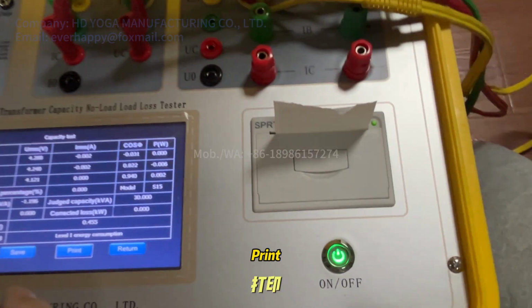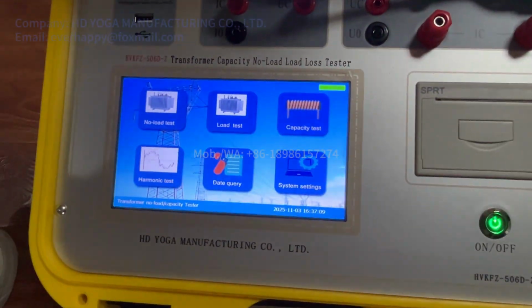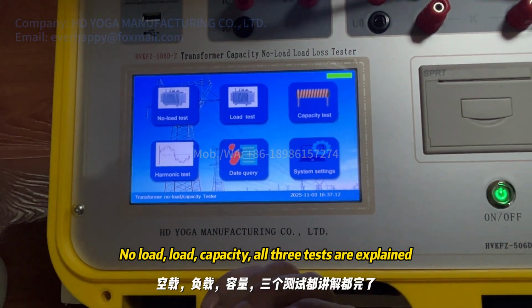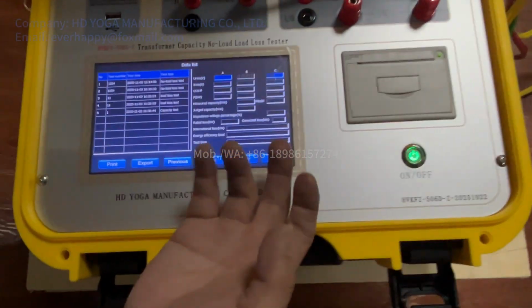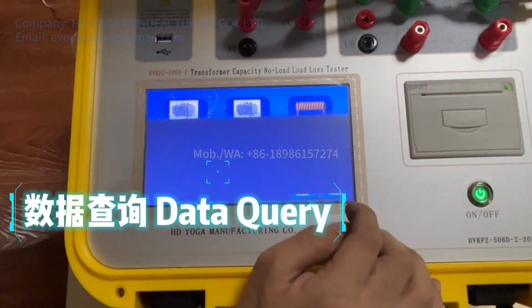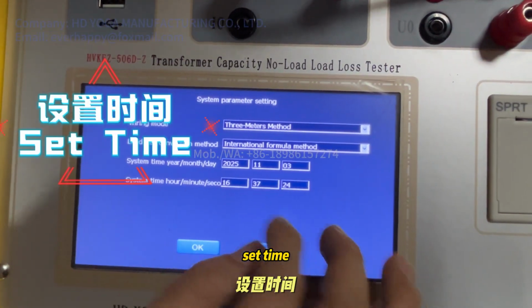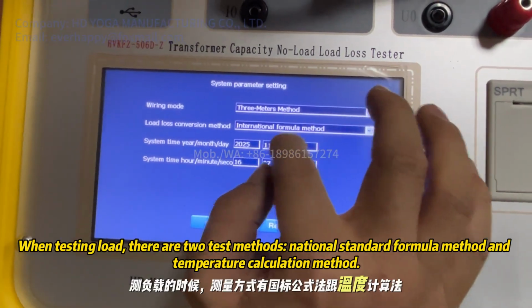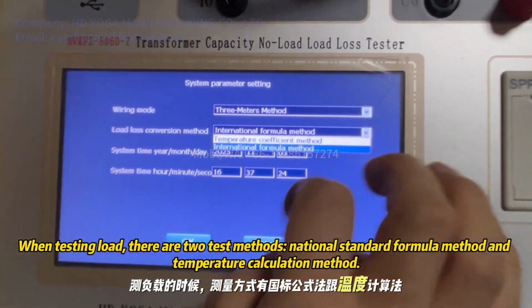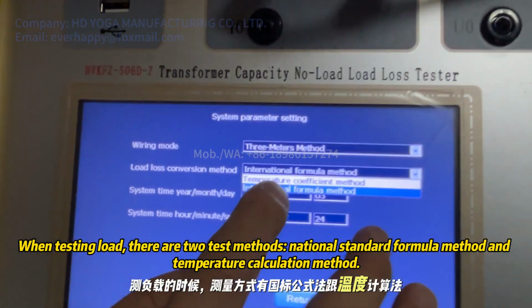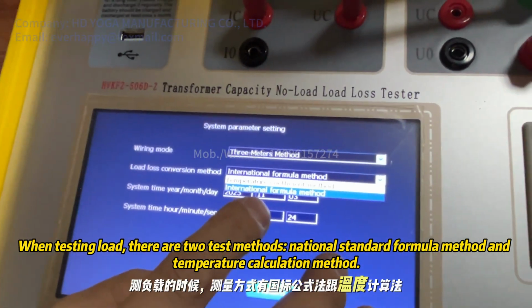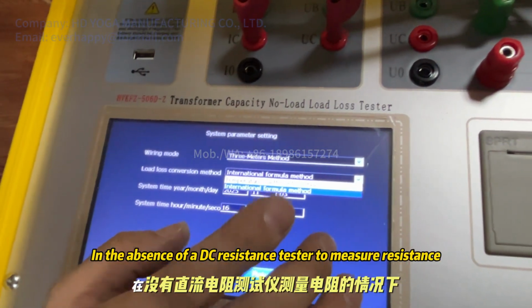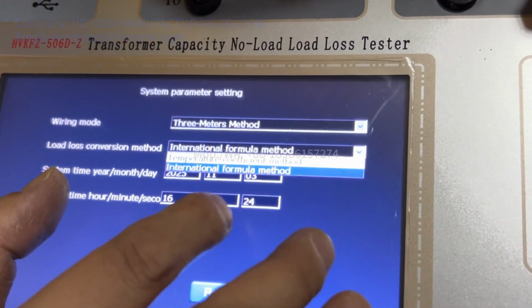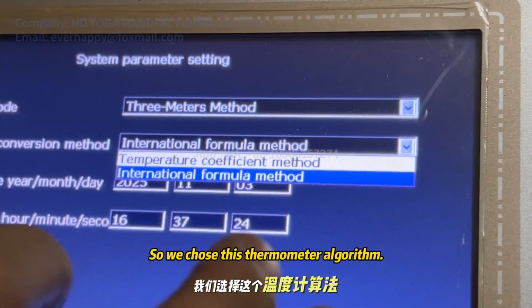The experiment is over. Click Save. Print. No load, load, capacity. All three tests are explained. Data query. Here is a setting. Set time. Then you can choose. When testing load, there are two test methods. National Standard Formula Method and Temperature Calculation Method. In the absence of a DC resistance tester to measure resistance, we chose this temperature algorithm.